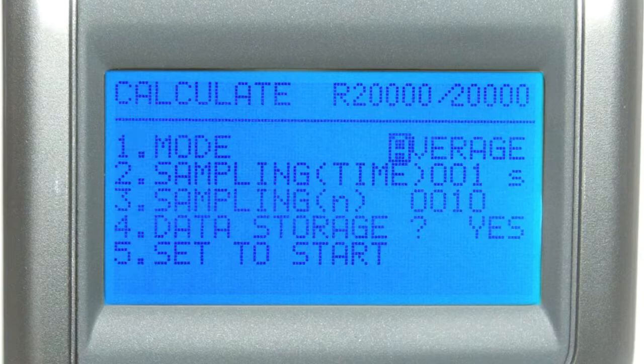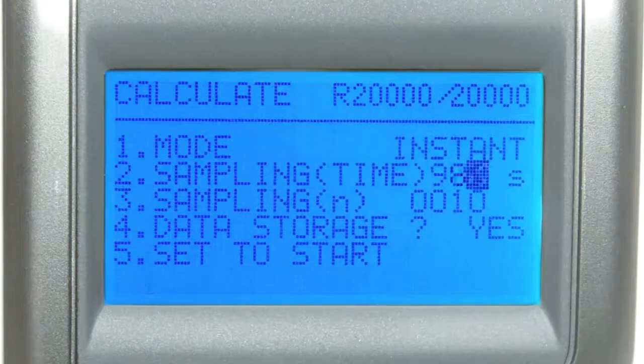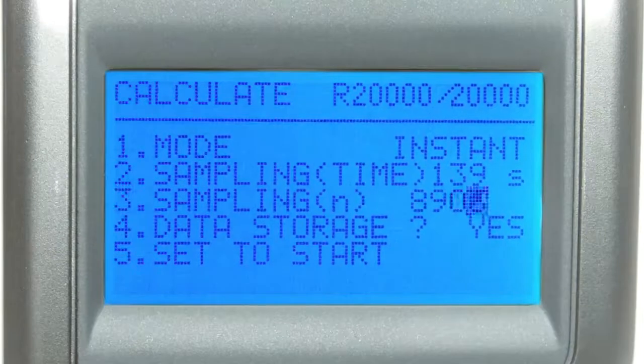Average takes a measurement every second and then displays the average for the set sampling time. Instant takes a single measurement at the end of the sampling time. Next is the sampling time, which can be set to any number of seconds between 1 and 999. Third is number of samples. You can set this to a number between 1 and 9,999. Fourth is data storage, which lets you choose whether or not you want to save each calculation on the Climomaster's memory. To save all changes to these parameters, select Set to Start.